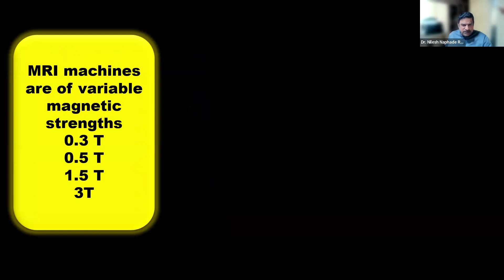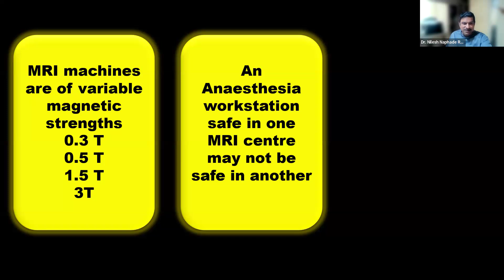An anesthesia workstation safe in one MRI center may not be safe in another. Why I am telling you this is that if you have an MRI center with a 0.3 Tesla machine, you have purchased an anesthesia machine for that center, telling the supplier that it's for 0.3 Tesla. Tomorrow you carry it to a 3 Tesla center, it may still get sucked because the magnet is more powerful than a 0.3 Tesla.